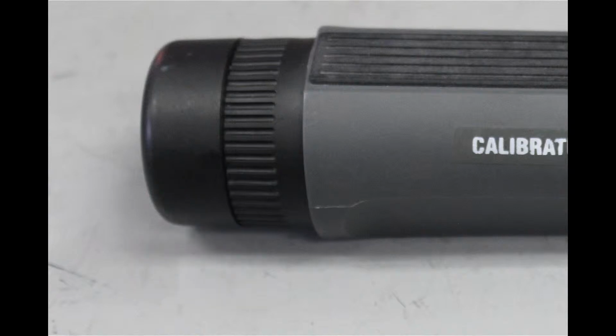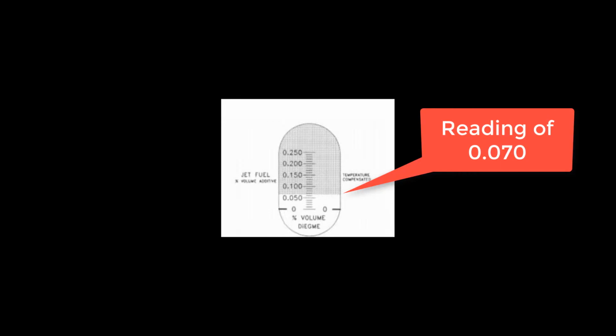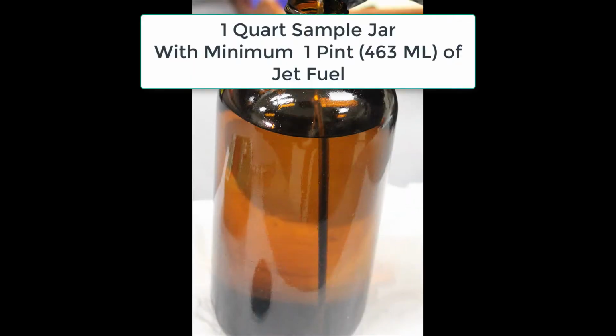When you go to calibrate it, you'll see this next slide here with the measurements that you'll see through the viewfinder. This is a zero reading that you'll see used during calibration when you use only water to calibrate. You see the gray line intersects at the 0, which is a perfect calibration. Here, this is fuel, or water that actually has DiEGME in it, and it measures at about 0.070% by volume at the gray line.